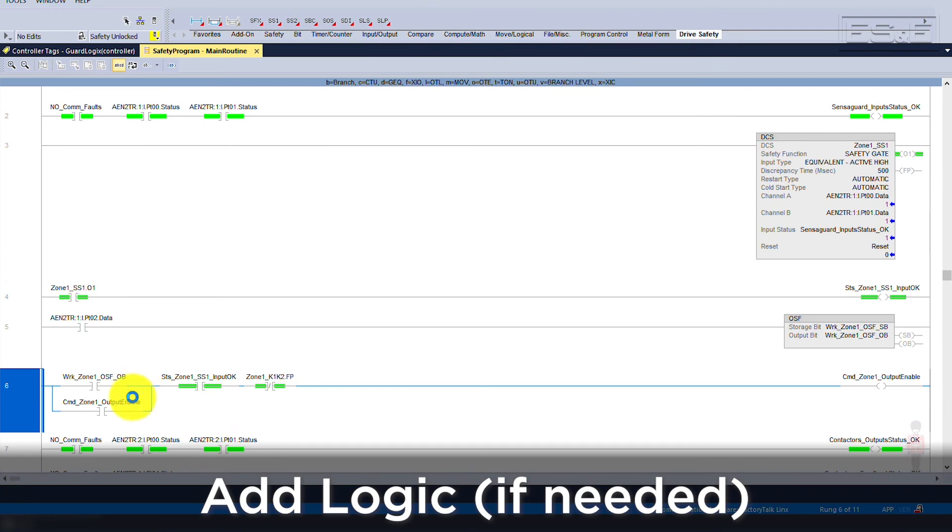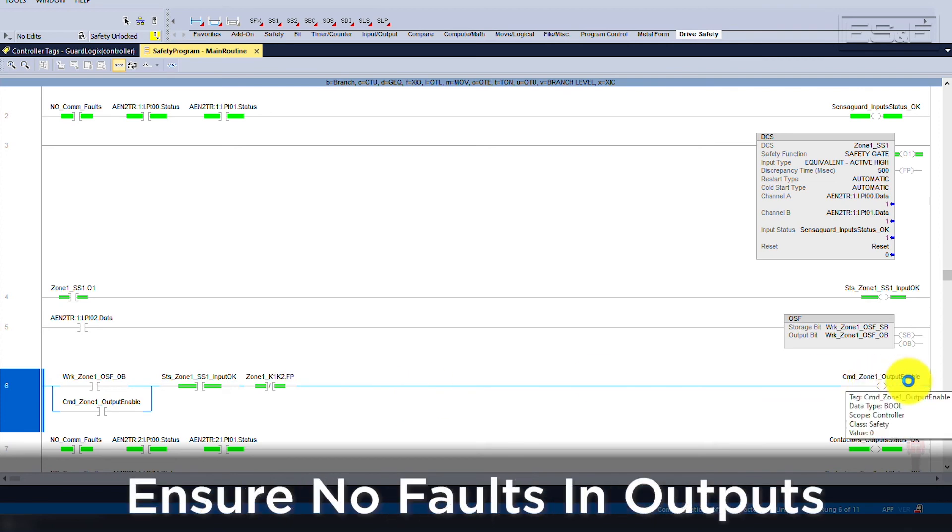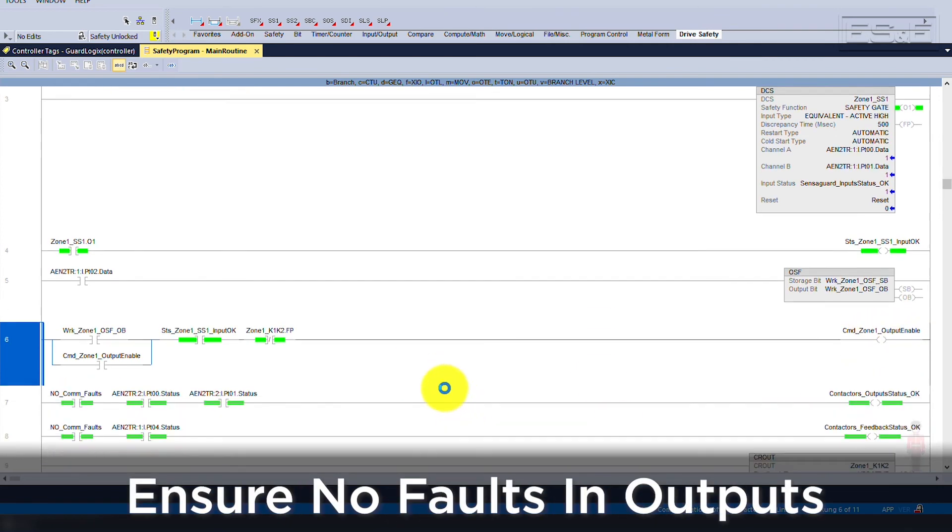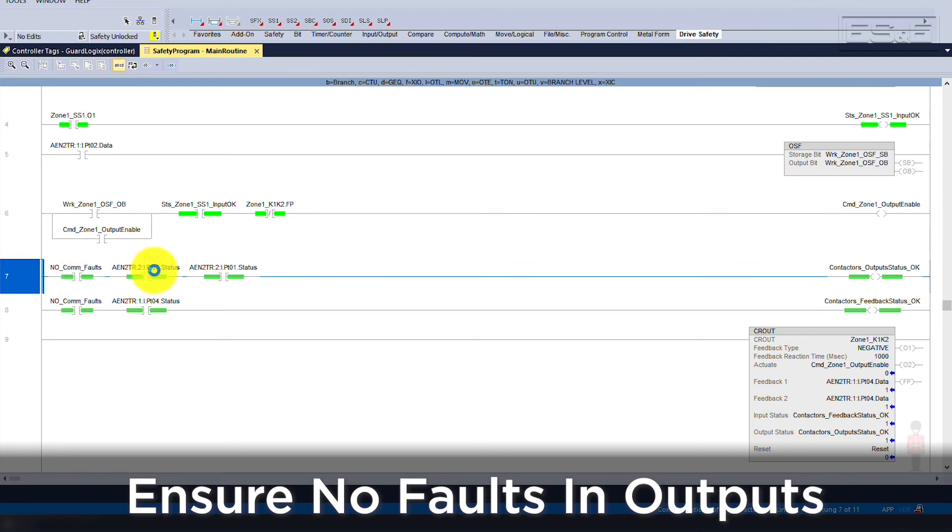The OSF in conjunction with the DCS output 1 can be used to enable your outputs. Most of the time, people will add additional logic at this rung to create a more dynamic system. Additional logic can consist of the machine sequence or output faults. After the outputs enable logic is created, we need to ensure that the outputs are not faulted, similar to what we have done for the inputs.